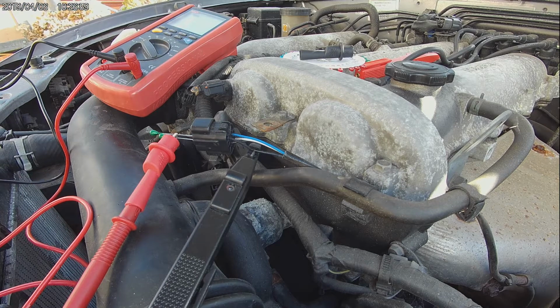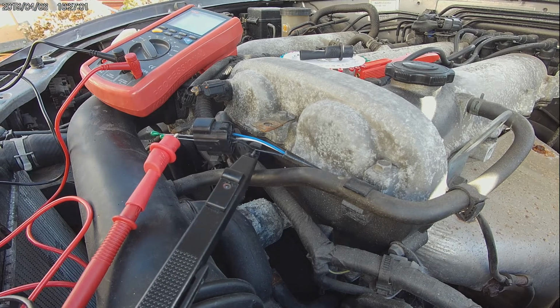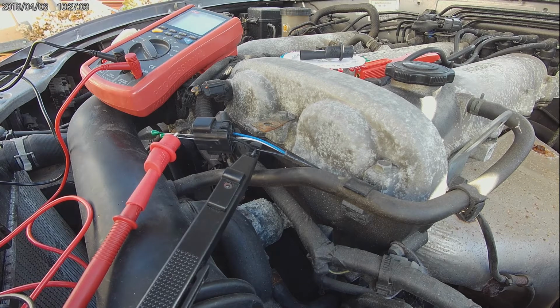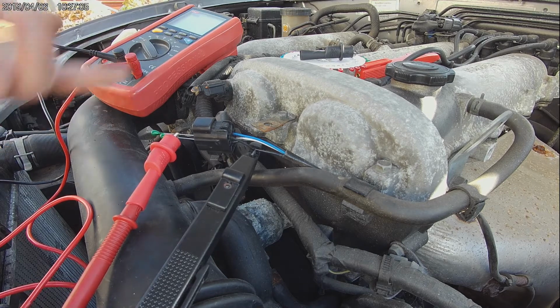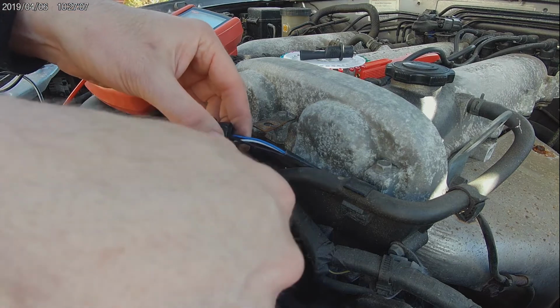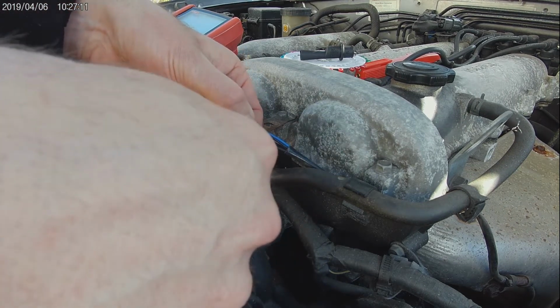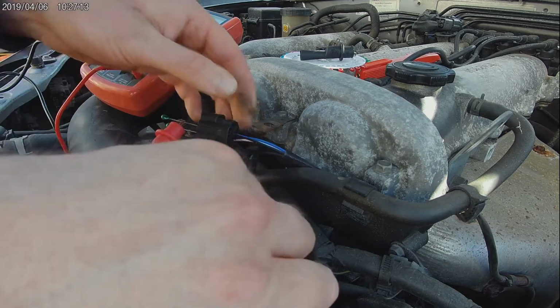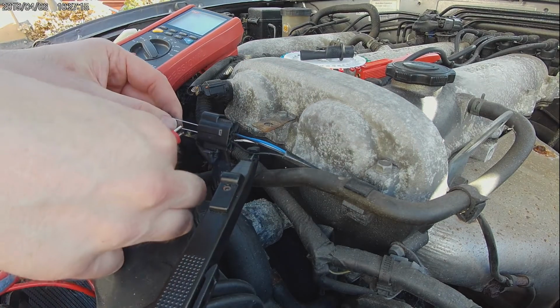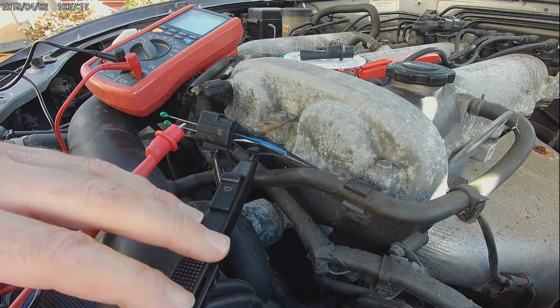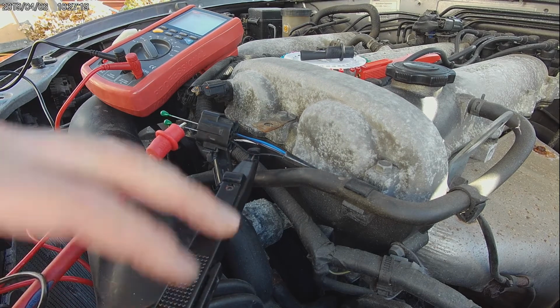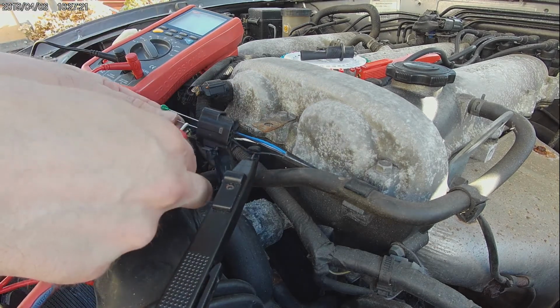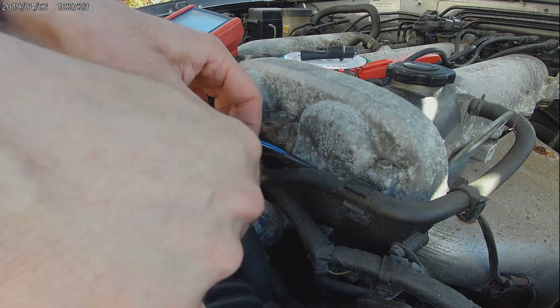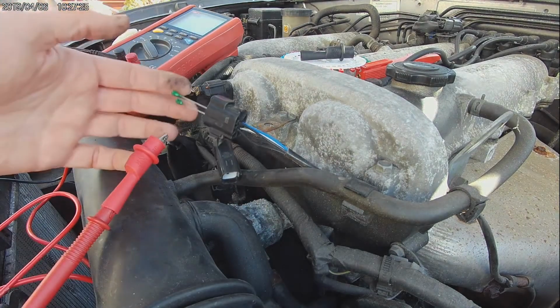So now what I'm going to do is just run the tester, and as you can see from the audible note of the tester, it's telling me that that back probe has made a circuit. So what I'm now going to do is I'm going to do exactly the same thing on the bottom wire. Swap my lead over just to make sure that we've got a circuit, and we have. So we know those back probes are working fine. So we've eliminated that the back probes are causing a problem.